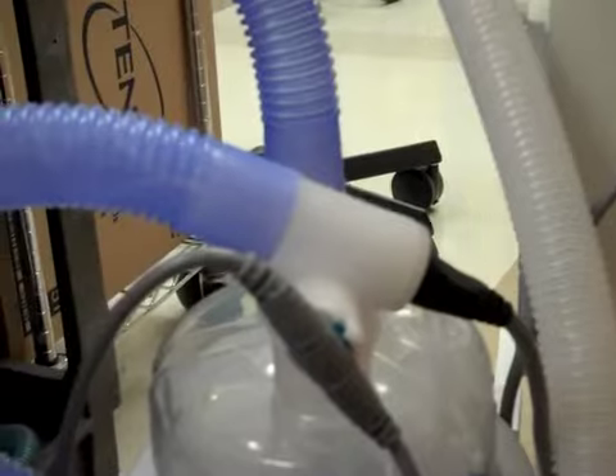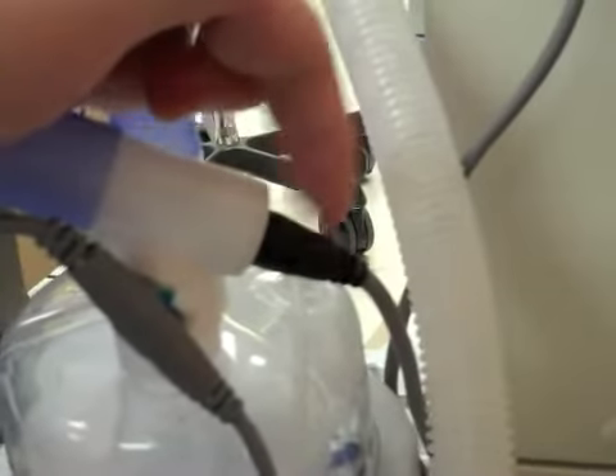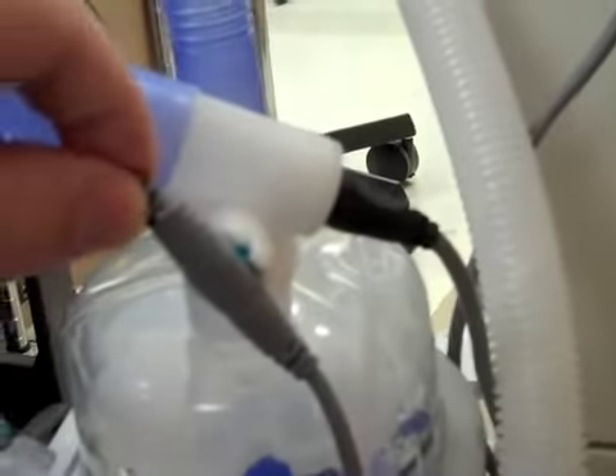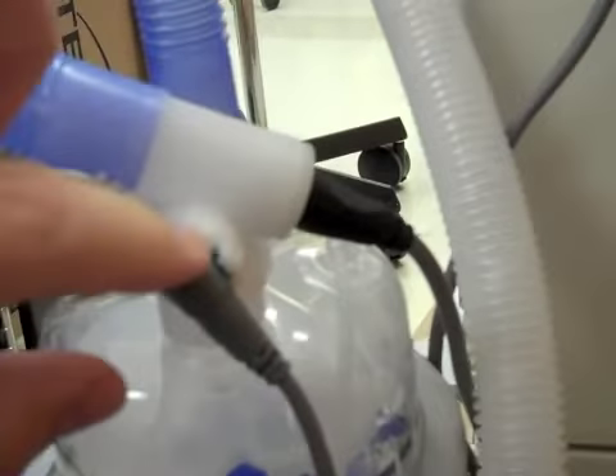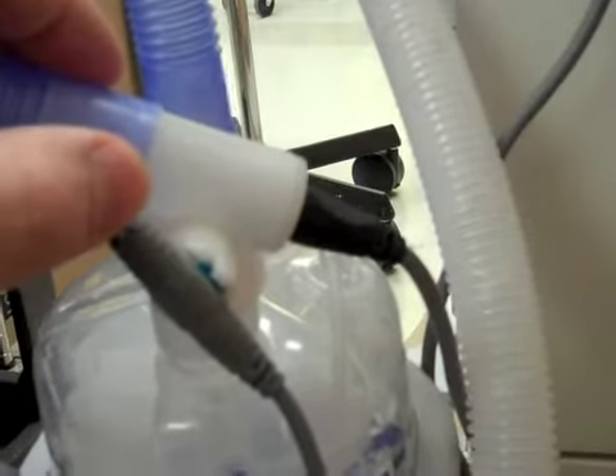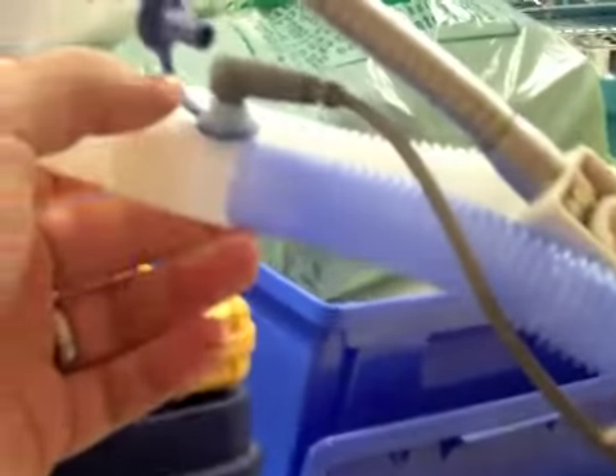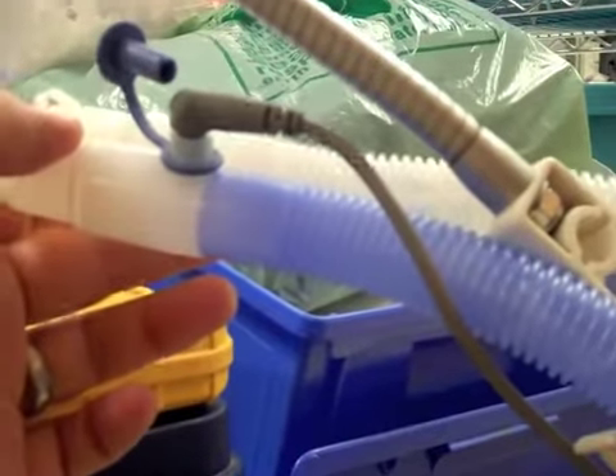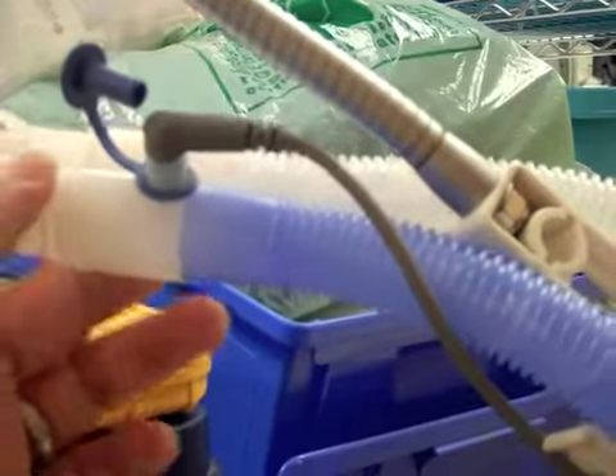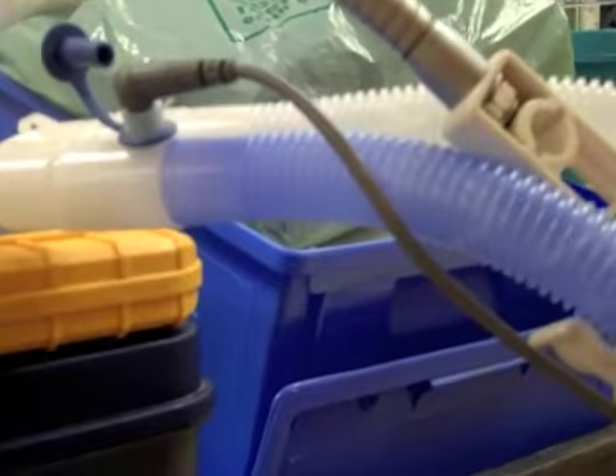You'll notice it's got the internal heater wire, which is powered by this heater cord here. I've got a temperature probe right at the chamber, so this is your chamber probe measuring the gas temperature of the gas leaving that chamber. I've also got a temperature probe closer to my patient, and it's measuring the temperature coming down that inspiratory side just before it enters into your patient.